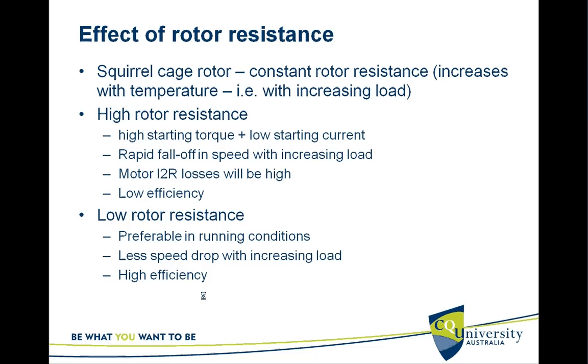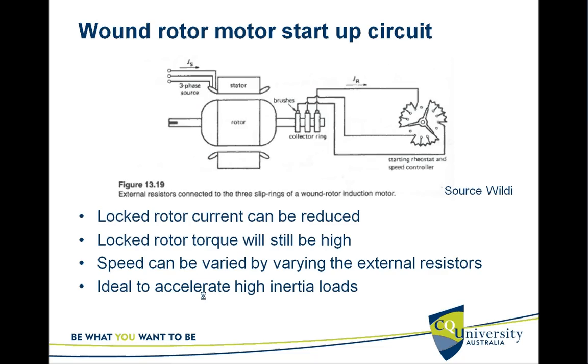For a wound rotor motor, it is possible to have a startup circuit. The rotor winding is taken out through three slip rings, and what we have is three star-connected variable resistors with equal tapping points of equal magnitude.